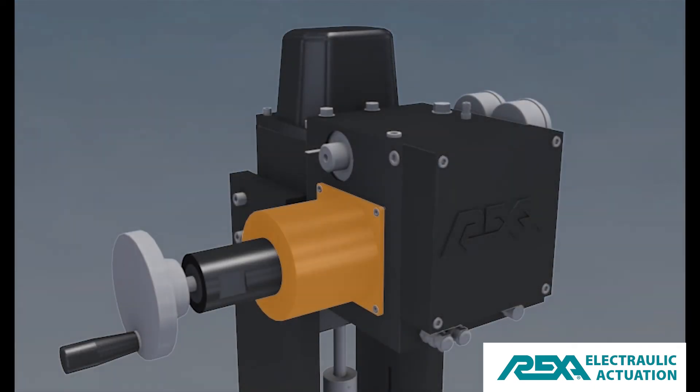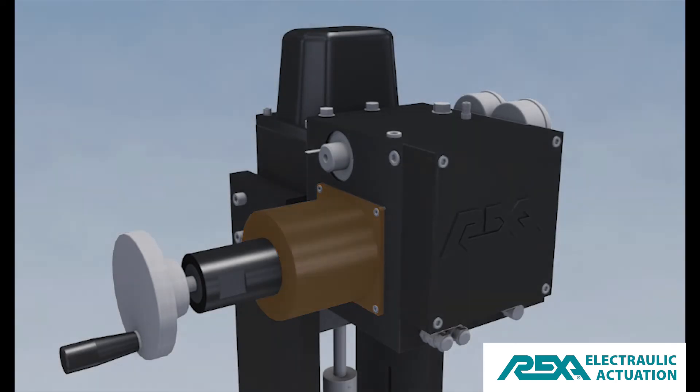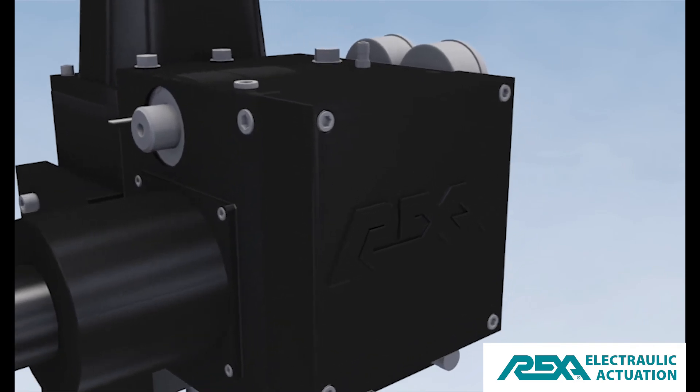The motor is a 100% duty cycle reversible unit which drives the internal hydraulic pump. The motor is either a stepper motor or servo motor. These motors are used because their speed and direction can be precisely adjusted by the control module to meet the performance required. The motor only activates when a valve position change is required, making it highly efficient.